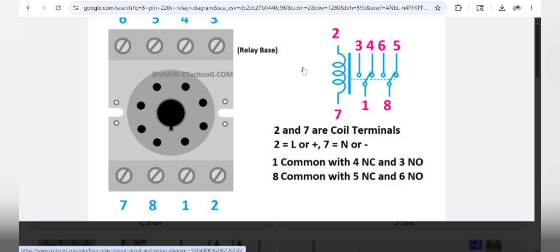As you can see, we can use just a 220 volt relay for this controller, or a DC volt relay, but the concept is the same and straightforward. So this is our 8-pin relay, 220 volt or 110 AC volt relay. This is the relay base and this is the relay block diagram. Pin number 2 and pin number 7 are the relay coil for energizing this relay, pin number 3 and pin number 6 are normally open, pin number 4 and pin number 5 are normally closed, and pin number 1 and pin number 8 are our common.